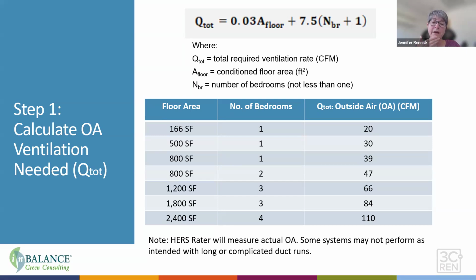And then let's say you had a 1,800 square foot house with 3 bedrooms. Now you're needing up to 84 CFM for outside air. And now you're going to be looking at multiple fans, or perhaps if you want the energy savings, you would go with the ERV or HRV. And then the prices vary depending on that type of system. But as architects, you have some control over that and what you might put into your project.